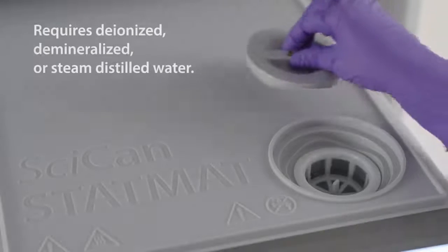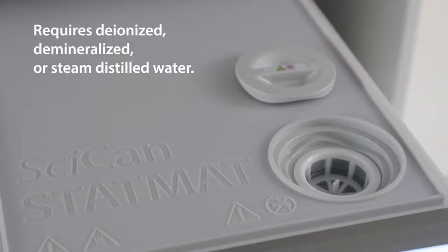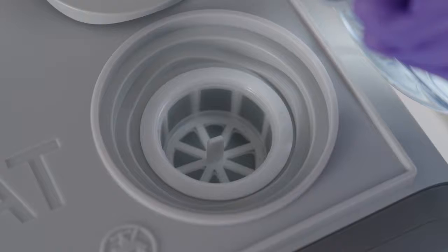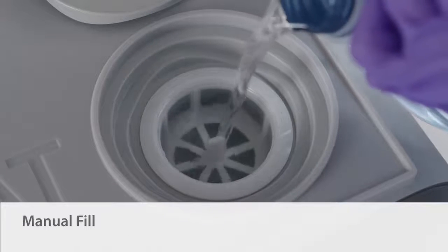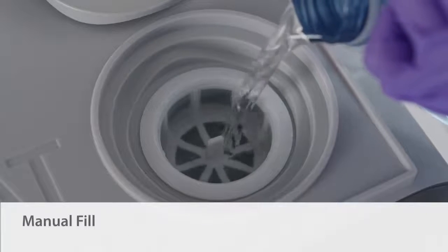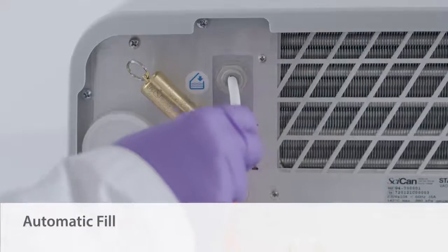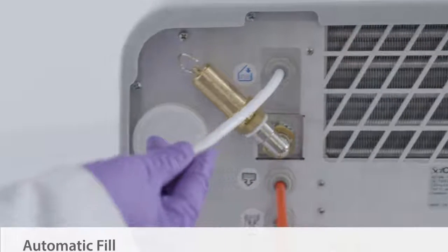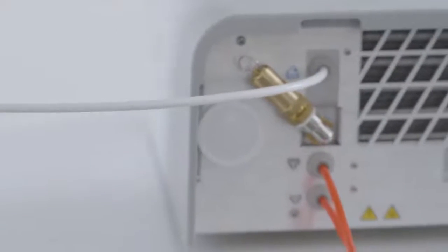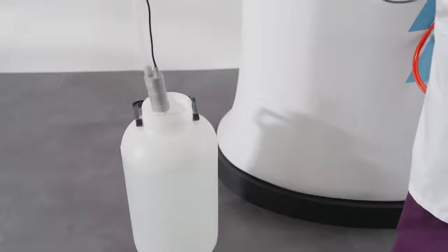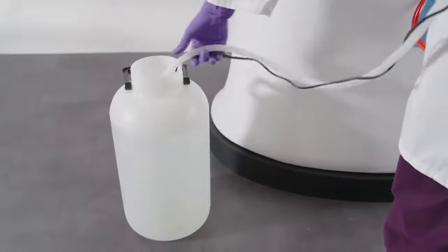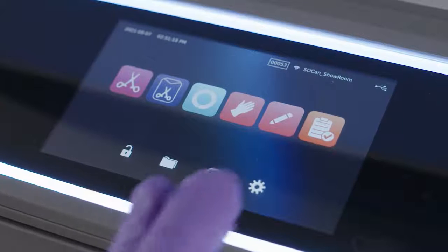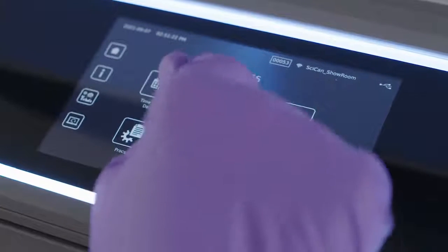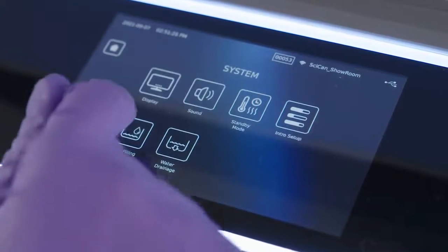The STATIM B requires deionized, demineralized, or steam-distilled water. Your STATIM B's default filling option is manual filling. This is done directly through the reservoir port on the top of the unit. STATIM B can also be configured to automatically fill the water reservoir using a water filtration system, or an external water tank with an auxiliary pump. If you are connecting your STATIM B to any of these external filling devices, make sure your unit is set to the automatic filling mode.